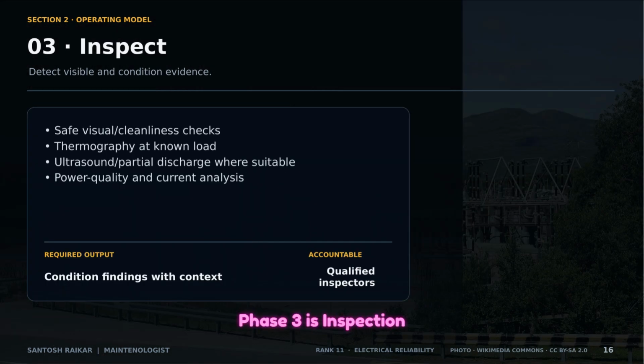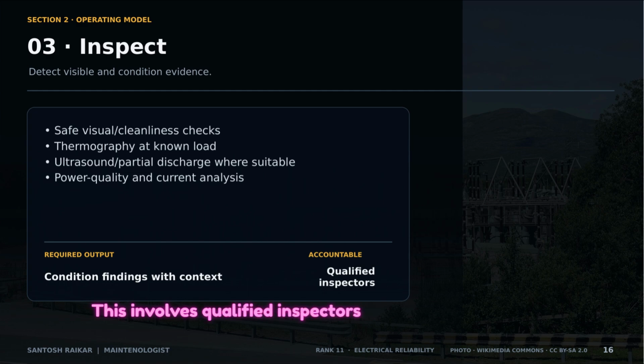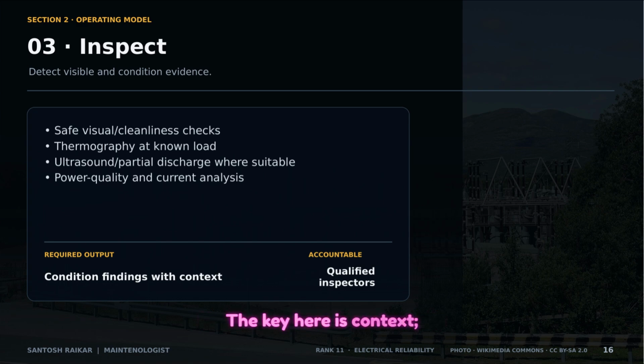Phase 3 is inspection. This involves qualified inspectors performing safe visual checks, thermography at known loads, and ultrasound. The key here is context. A temperature reading means nothing if you don't know the load on the circuit at that moment.